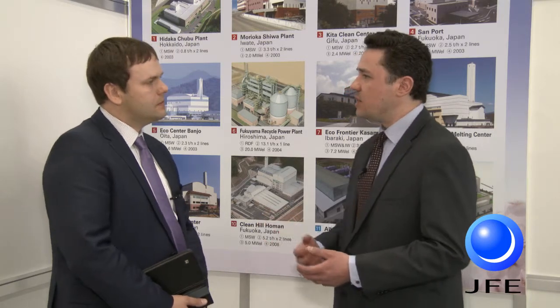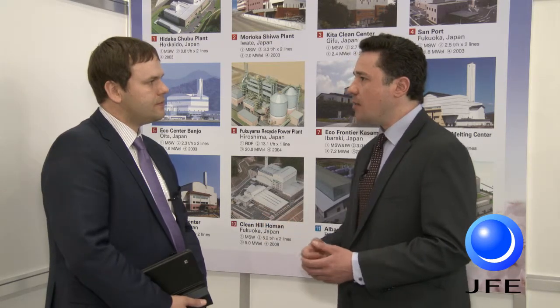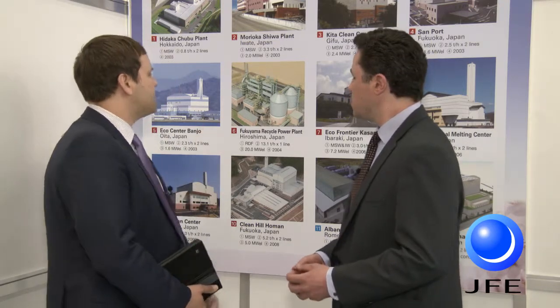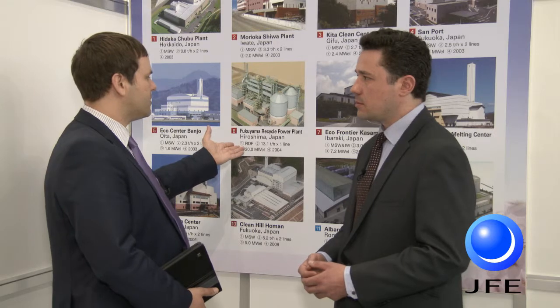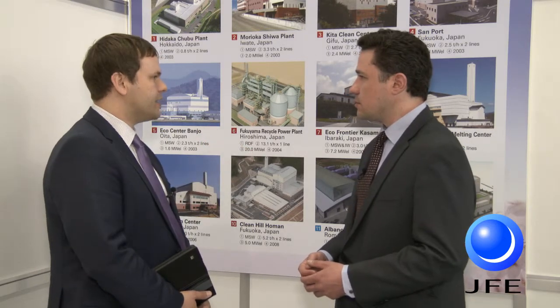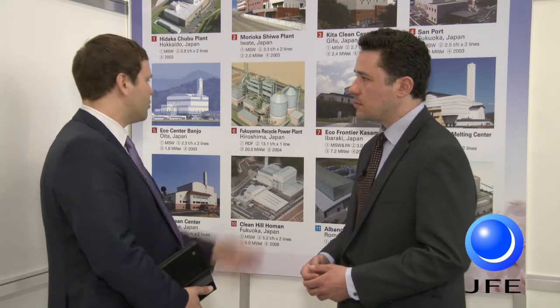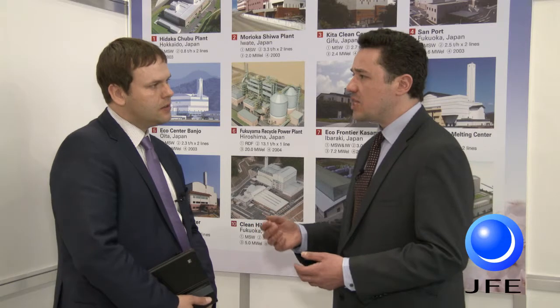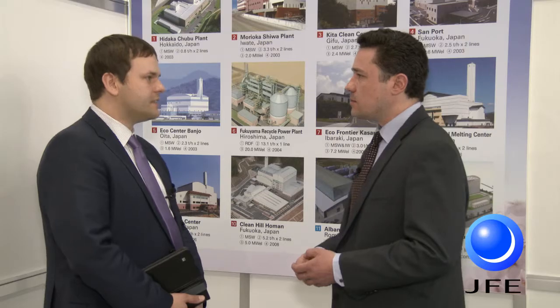The Fukuyama facility is processing RDF, so the municipal waste has been processed prior to being used as fuel. This plant is designed to operate with high calorific value RDF — the feed is about 16 megajoules in the RDF — and the electrical output is about 20 megawatts. The design of the system does not change much between RDF and municipal solid waste; it is basically the same.